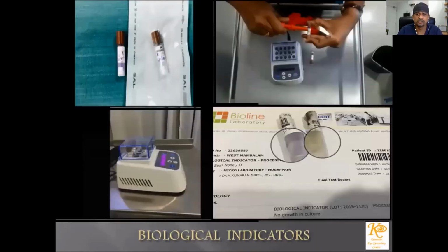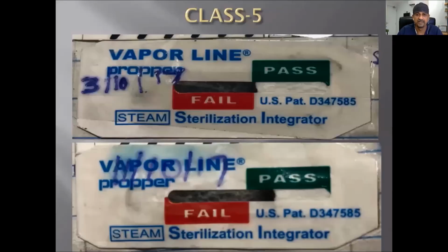A small note on the biological indicator, in terms of 2 vials. 1 vial is sterilized, and after it comes out, the control and the vial are processed after the inner tube is broken. The vial which is processed inside the autoclave does not turn yellow in color, but the control turns yellow in color. The biological indicator has to be used for every load in every cycle.